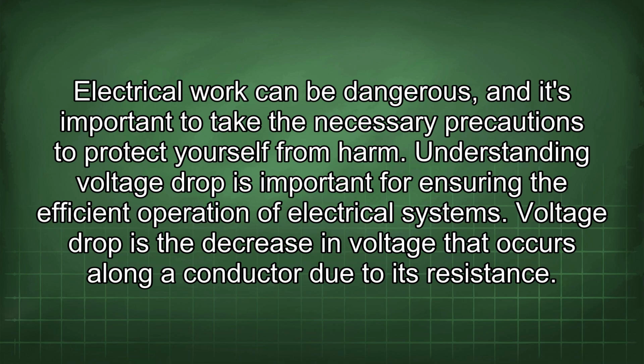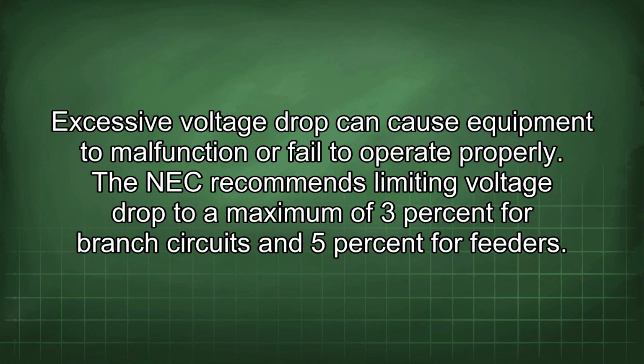Understanding voltage drop is important for ensuring the efficient operation of electrical systems. Voltage drop is the decrease in voltage that occurs along a conductor due to its resistance. Excessive voltage drop can cause equipment to malfunction or fail to operate properly. The NEC recommends limiting voltage drop to a maximum of 3% for branch circuits and 5% for feeders.